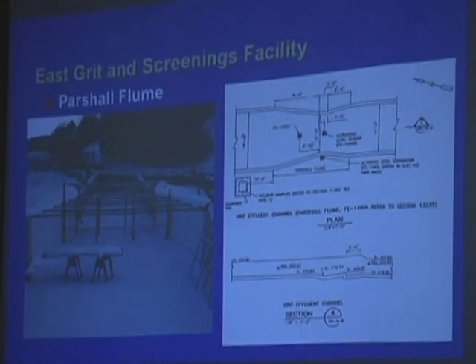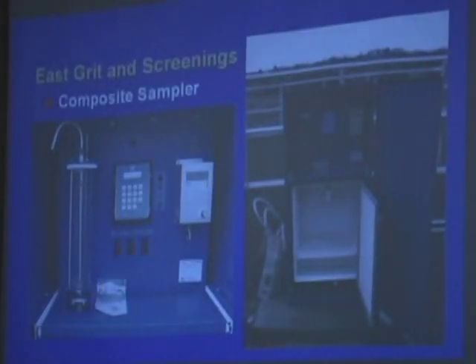The drawing on the right-hand side indicates where the flow measuring devices are. Flow and level measuring devices, one located on the upstream side, one located on the downstream side, and it gives you some elevations of the flume itself. At the flume, there's an automatic sampler, which is set up to receive a flow signal from the flume itself to get a flow proportion sample.